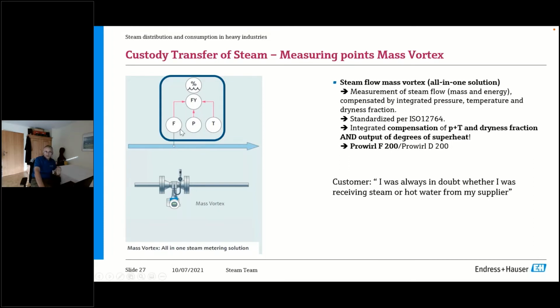And in addition, in case you have a contract for superheated steam and you have a guaranteed amount of superheat, you can always check that and you can use the output of that vortex meter to say, hey, Mr. Supplier, I'm getting overcharged because my steam for 15 hours last month was less than 5 degrees C or 5 Kelvin superheated. So that really gets rid of that doubt if you are receiving steam or hot water from your supplier. So that's really the best solution for such cases.